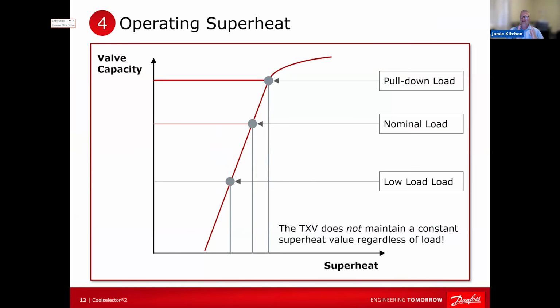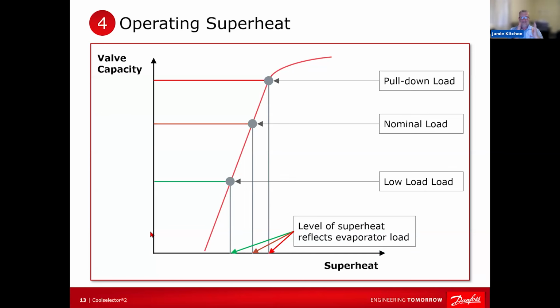But generally speaking, if you're under high load, think we can either do a walk-in box or a dwelling or whatever. But think you have a room that has a certain load. A whole bunch of people start moving around in there, and people give off latent and sensible heat. There's equipment in there firing up, whatever. You increase the heat load on this evaporator. The TXV now is going to start to open up, but you will still see a slight increase in superheat. It's not going to be a lot, right? But it will be a slight change in superheat.